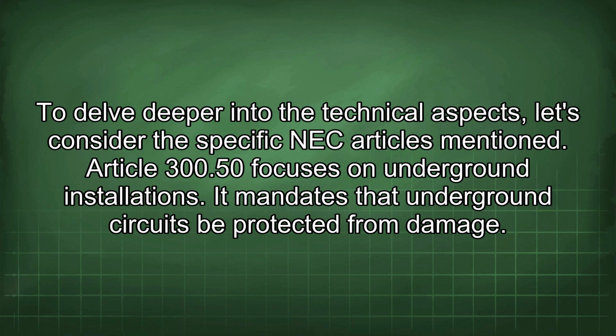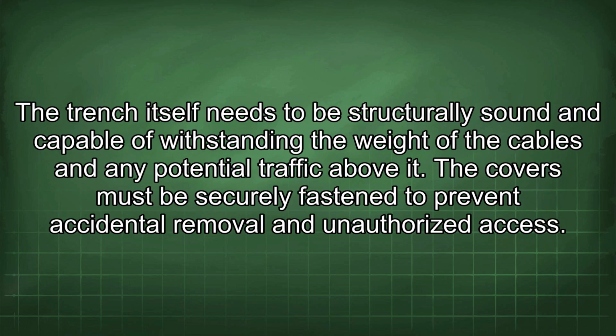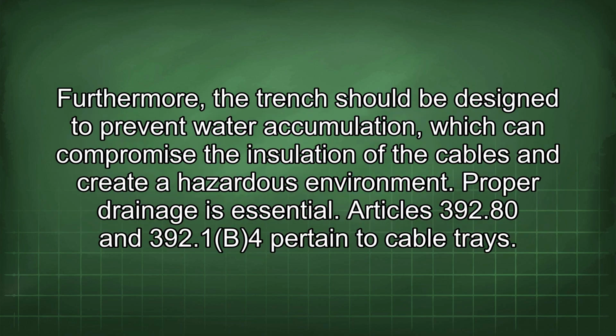Article 300.50 focuses on underground installations. It mandates that underground circuits be protected from damage. The trench itself needs to be structurally sound and capable of withstanding the weight of the cables and any potential traffic above it. The covers must be securely fastened to prevent accidental removal and unauthorized access. Furthermore, the trench should be designed to prevent water accumulation, which can compromise the insulation of the cables and create a hazardous environment.